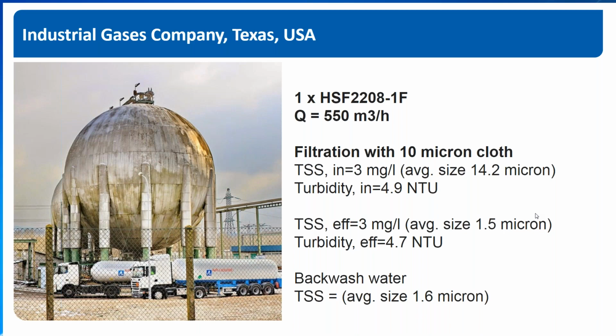Great. Another one is, what are the typical recommended coagulants and polymers? And are they any different than what is typically used for a clarifier? And then finally, last part of that question, is there a risk of blinding the filter cloth? Okay, so to answer the first question, it's really case by case. This is something that we would need to evaluate depending on the water source. If you've got a specific scenario, you can send a mail and we can tell you about our experience there. In a very similar case, but it does depend.